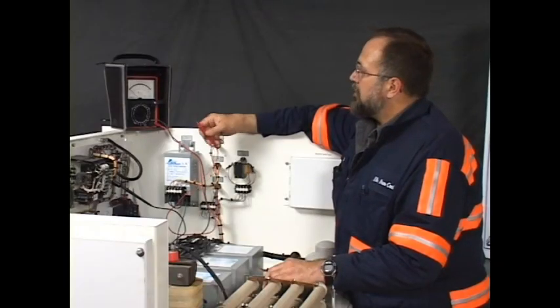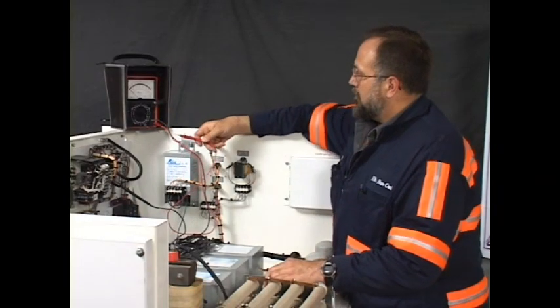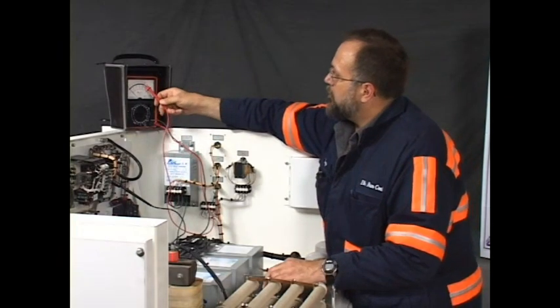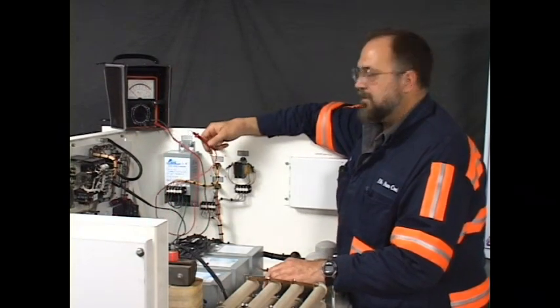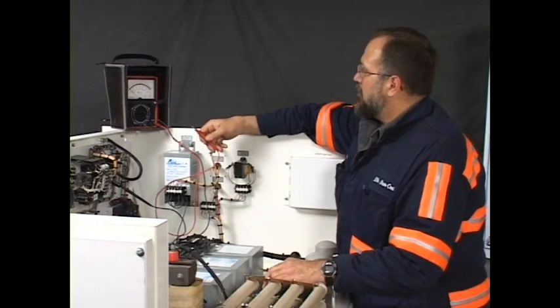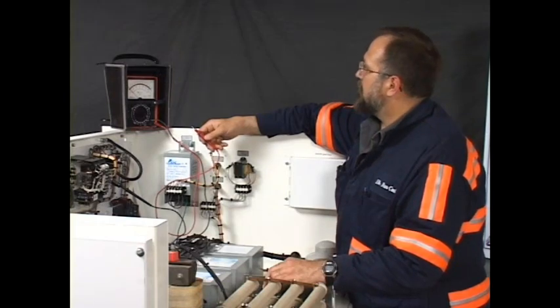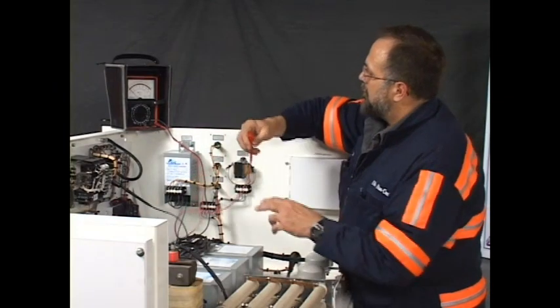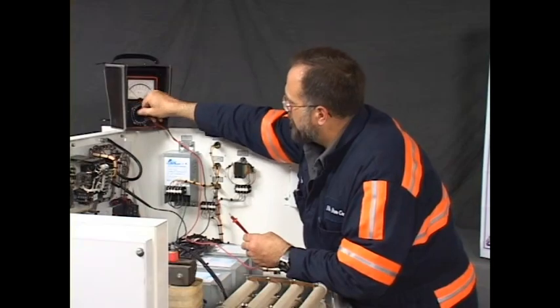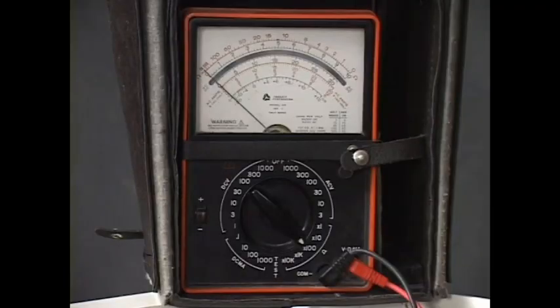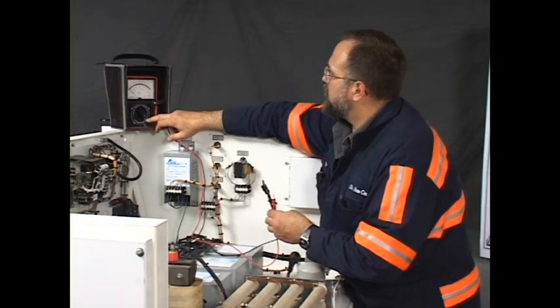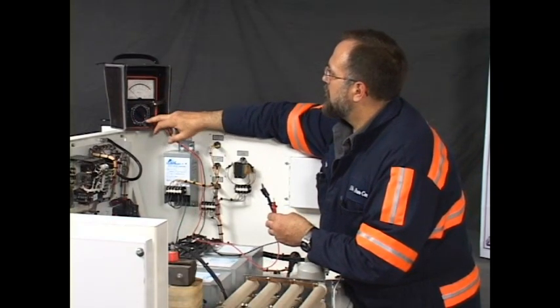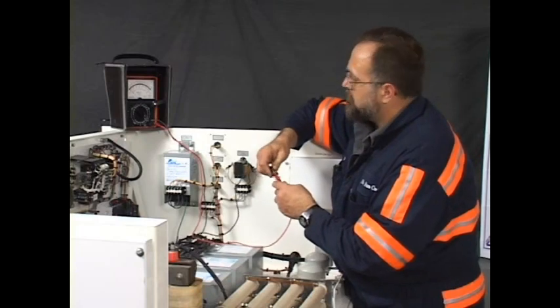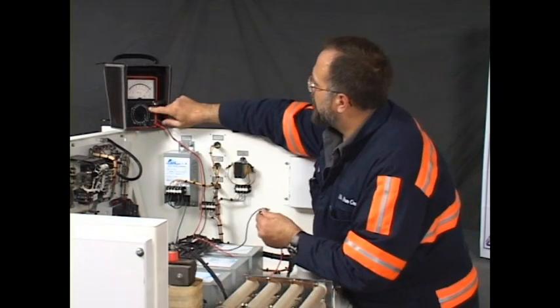So we need to choose a scale, a multiplier, that will be easy to read, that'll put us somewhere in the middle of the meter. By the print stating it's a 500 ohm resistor, I'm going to choose something that would be easy to read: times 100. So whatever this needle indicates, times 100, will be my reading. I'll change scales and we'll recalibrate the instrument. Oh, it's not really off much on that scale.